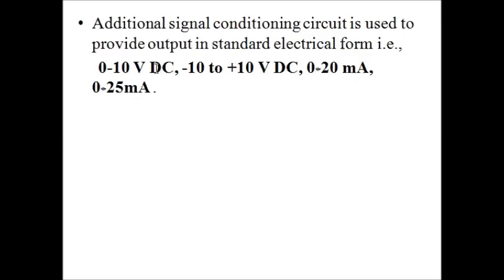The output signal of a transducer is basically a voltage or current signal within the following standard ranges: 0 to 10 V DC, or minus 10 to plus 10 V DC for voltage; and 0 to 20 milliampere or 0 to 25 milliampere for current.